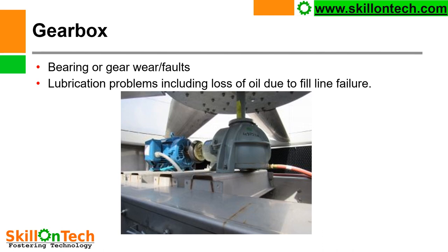Gear box is a very important part for operating the cooling tower fan, which is directly connected with the gear box shaft. Gear box bearings or gears may wear or become faulty and shall be inspected during shutdowns. If any problem is observed during predictive maintenance or inspection of the gear box, they shall be rectified. The gear box may have lubrication problems due to loss of oil or fill line failure. Gear box oil shall be topped up time to time to maintain lubrication of gears and bearings. If there is any problem in the fill line of lubrication, it shall be replaced.